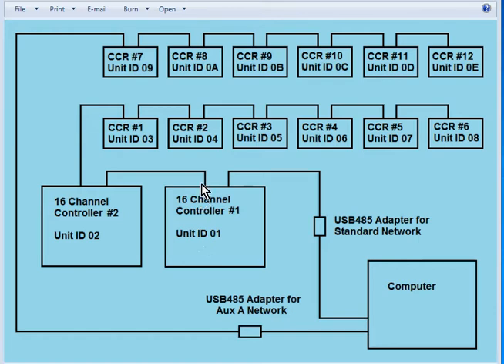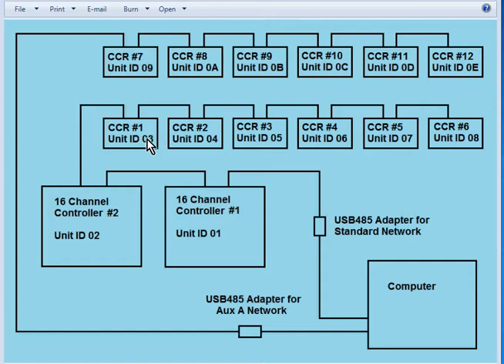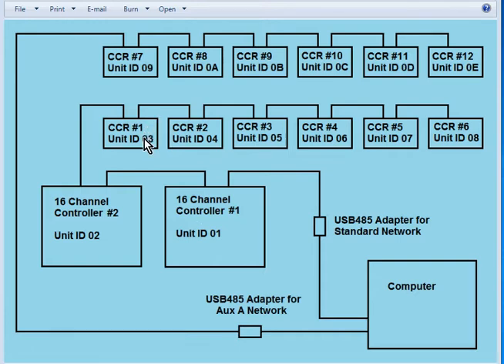And he has unit ID 01. He is daisy chained to my second 16 channel controller and he has unit ID 02. He is daisy chained to CCR number 1 which has unit ID 03. Note that I could not use unit ID 01 here because each controller has to have a unique unit ID. And this controller down here already took 01, so I assigned him 03.